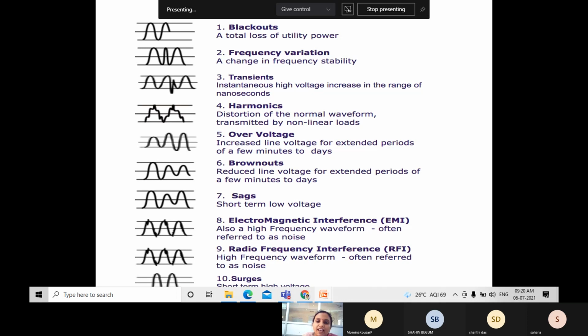Okay. A transient means an instantaneous high voltage increase in the range of nanoseconds. For example, if it is 1 kilovolt, suddenly it increases to 2 kilovolts, and that too for a few nanoseconds. It will increase and then come back to normal. Okay, that is a transient: an instantaneous high voltage increase in the range of nanoseconds.